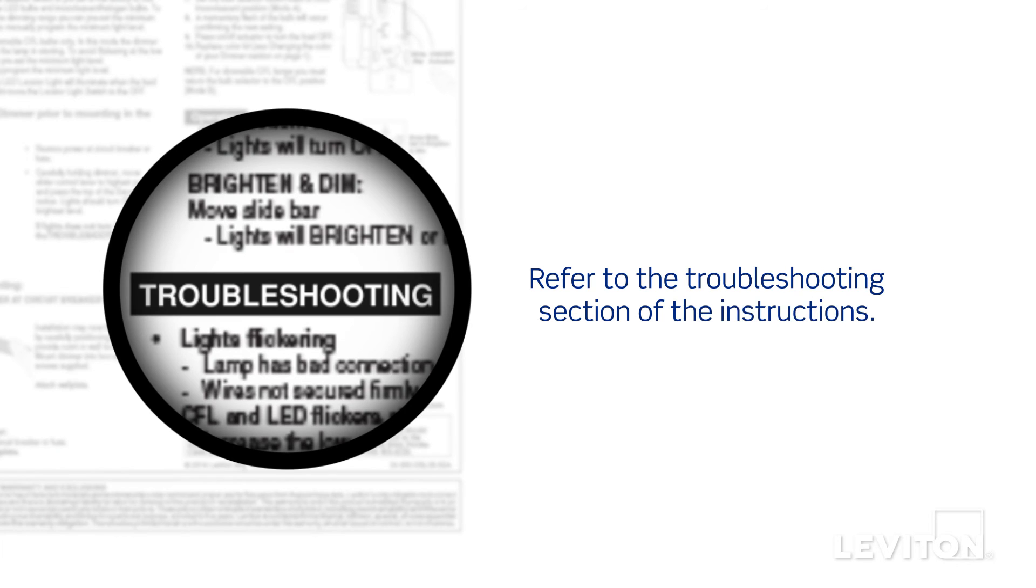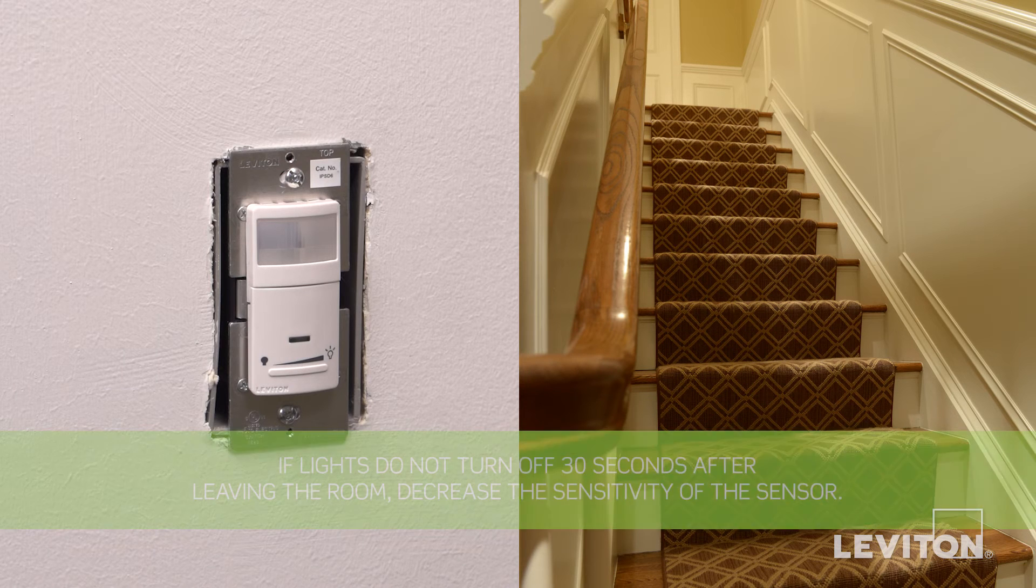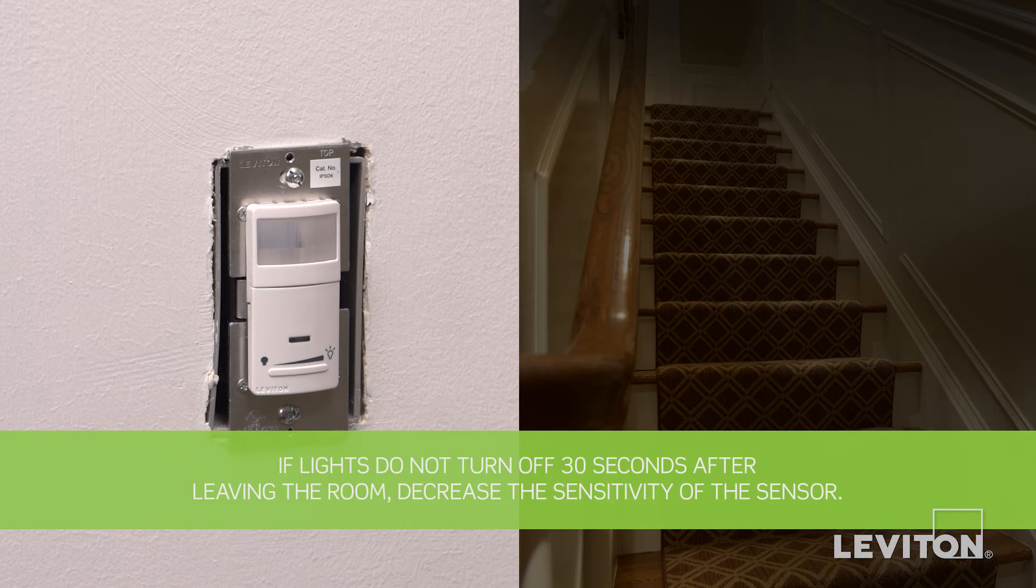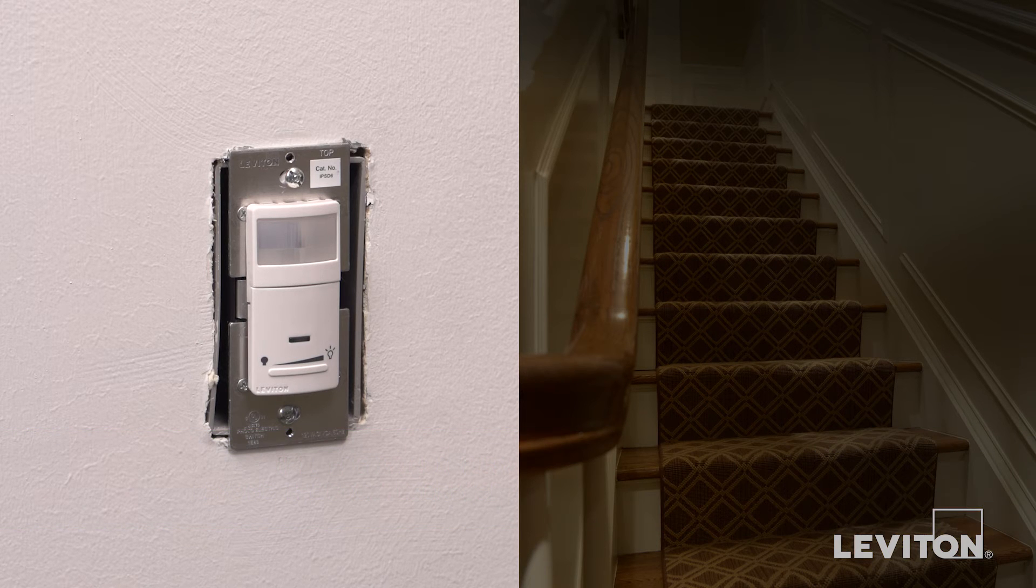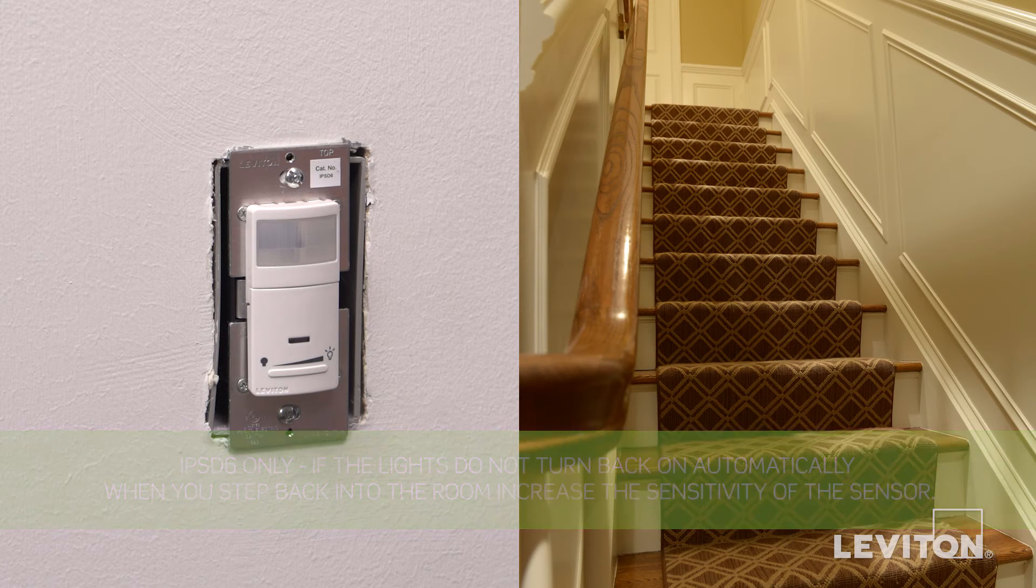Note, if lights do not turn on, refer to the troubleshooting section of the instruction sheet. Leave the room or field of view to allow the sensor to timeout and shut off the lights due to the absence of motion. Within 30 seconds of the lights timing out, step back into the room or field of view of the sensor and the lights should turn back on automatically.